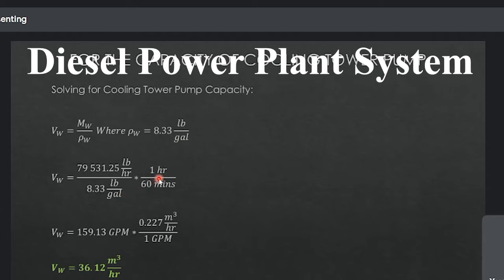Need natin i-convert into minutes, so that would be 159.13 GPM. Pero cubic meter per hour yung gagamitin natin kasi sa next requirement natin, kailangan natin hanapin yung brake power ng pump. Convert lang natin siya: for every 1 GPM, meron tayong 0.227 cubic meter per hour. So ang total volume natin ngayon, or ang capacity ng cooling tower pump natin, is 36.12 cubic meter per hour.